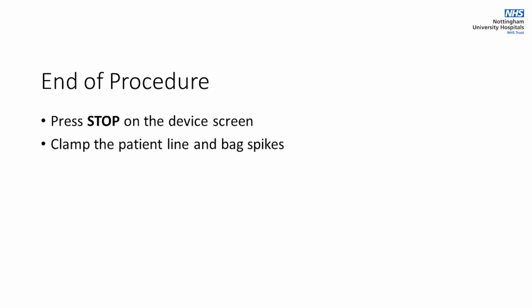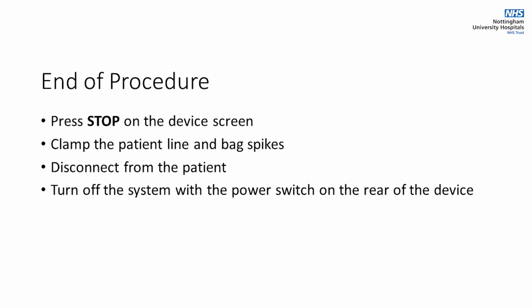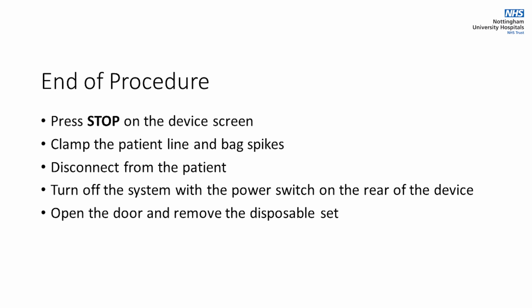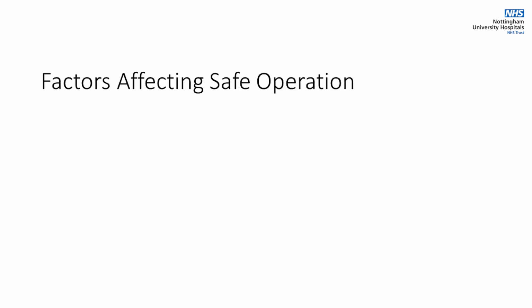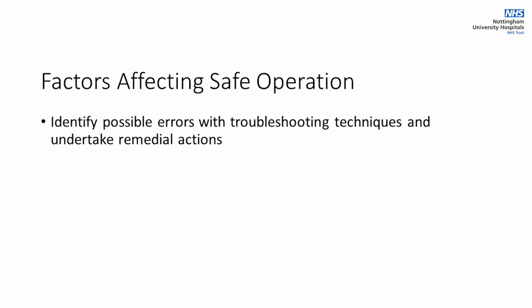What to do at the end of the procedure. Press stop on the device screen. Clamp the patient line and bag spikes. Disconnect from the patient. Turn off the system with the power switch at the rear of the device. Open the door and remove the disposable set. What factors may affect the safe operation or accuracy of the device? Please identify possible errors with the troubleshooting techniques and undertake remedial actions.